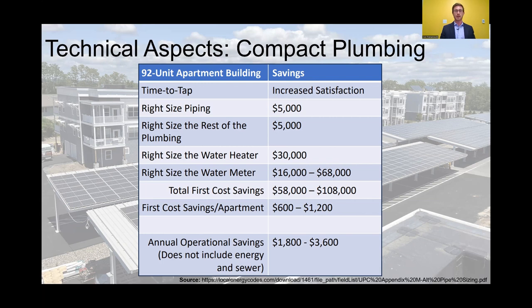Let's take a look at the additional savings. Well, you right size the piping, you save some money. You get to right size the rest of the plumbing based on your smaller piping. So insulation and hangers, things like that, all get to be smaller because you have smaller pipes. Now you've got smaller pipes, there's less water circulating throughout the building and less heat loss. So you can right size the water heater, and then you can right size the water meter.